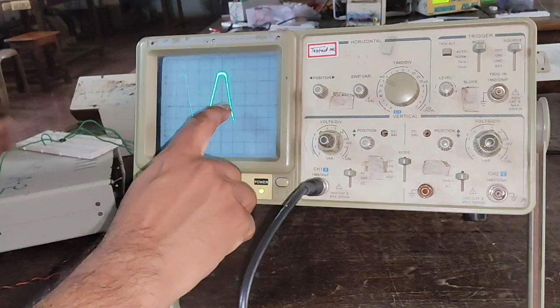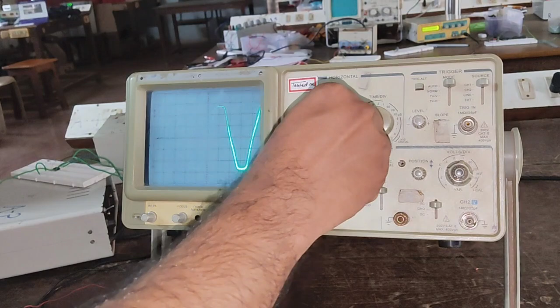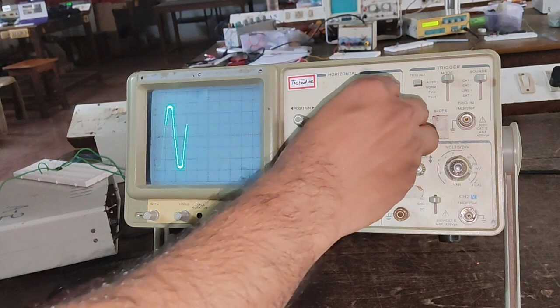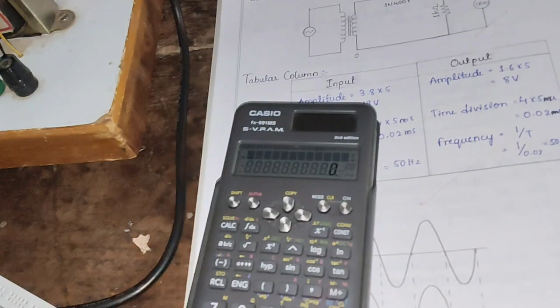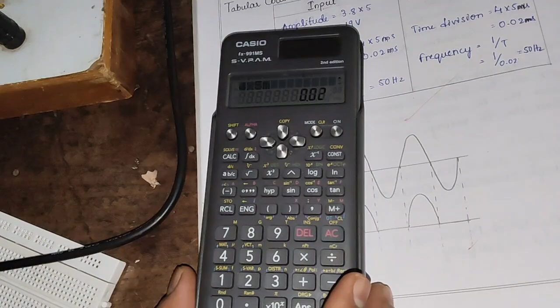Now we measure its width. From 0 we count 1, 2, 3, and 3.8, with the calibration button kept at maximum. Measuring once again: 1, 2, 3, 4, that's 4 into 5 milliseconds, totaling 0.02 seconds. Taking 1 divided by this, that gives 50 hertz.